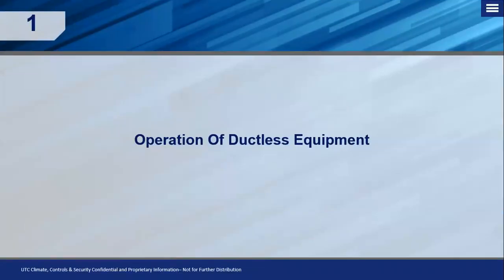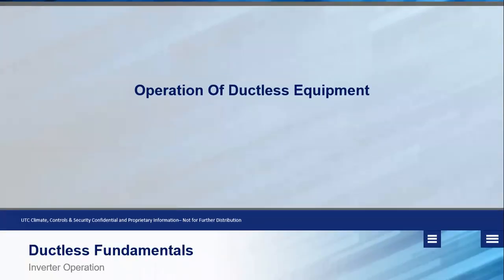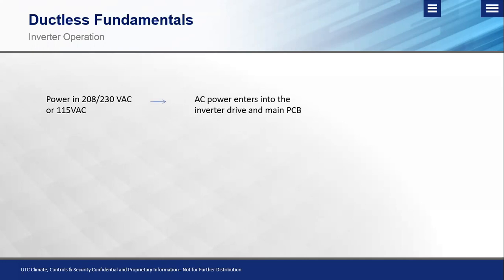So the basics, or the basic operation, of ductless equipment. No matter whether we're dealing with a single zone or a multi-zone, or whether we're dealing with 208, 230, or 115 volt single phase only power, we're going to have that power coming into the outdoor unit to run the machine. From there, we're going to take that AC incoming voltage, and it is going to enter into the main PCB board, or the main board in the outdoor unit. Now, these boards will differ depending on what kind of unit you have. There are some, such as the multi-zones, where we have a split type board, with a main PCB and an inverter drive. And on the single zones, depending on the tonnage, we just have one integral board that is an inverter drive and a main PCB board in one. But nonetheless, we have that AC power that comes in and powers that board.